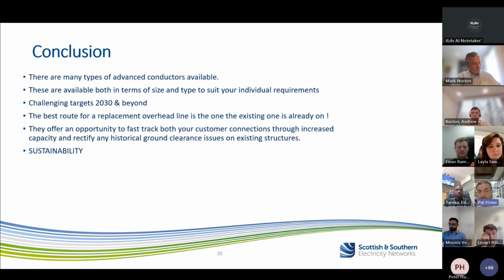The reason I brought this one to you is we've all got this 2030 date hanging over us. We're trying to get as many customers connected as possible - the number of connections is huge, and the pressure on us to get all this done is also significant. So this offers a chance to keep our existing line structures in place. As you know, when you normally go to a bigger conductor, you need to shorten span lengths and look at extra structures - that's not the case if you go for this type of conductor.